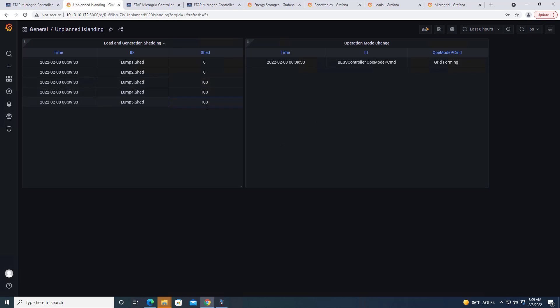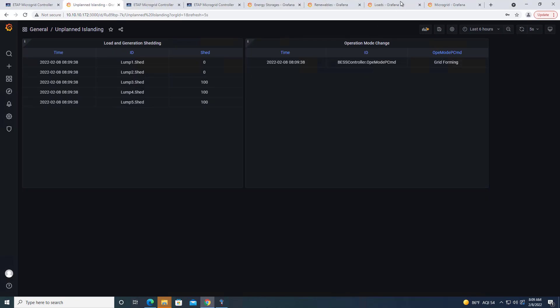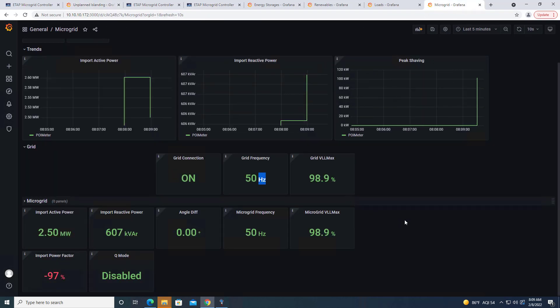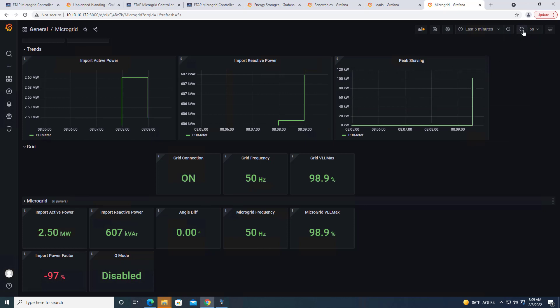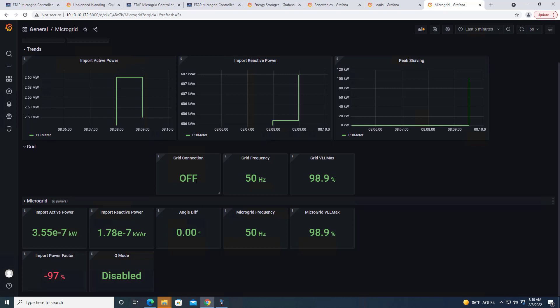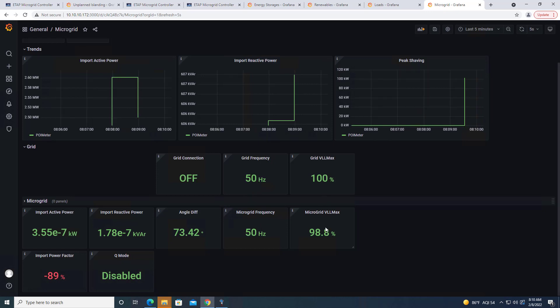Because this information is already transferred to the gateway in the simulation, it knows what to do. It doesn't need to wait. So we go now to the microgrid and let's look at the microgrid here. In about a few seconds, we should go off. Let me just reduce the resolution here. We see that we are in the grid connection on, and in about a few seconds we should transition to off. There you go. Now we are in the islanded mode. Things happen very quickly. In less than a second, system gets back to normal. You see that both side frequency are 50, system didn't collapse.